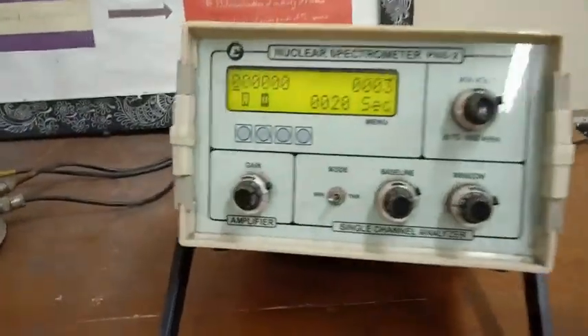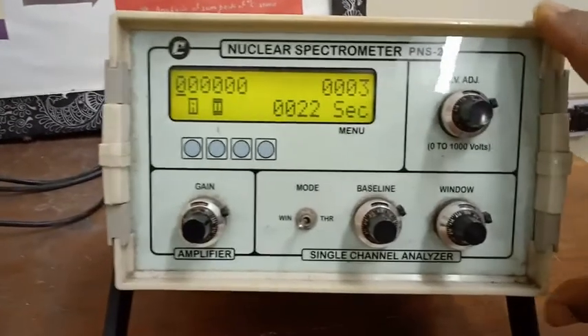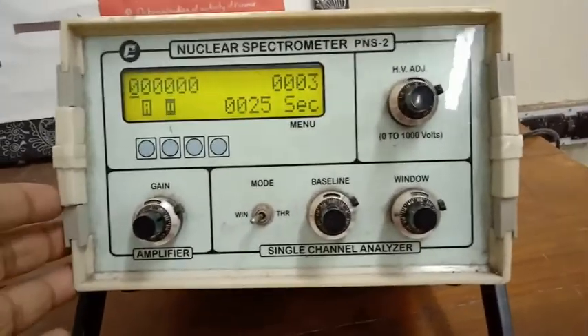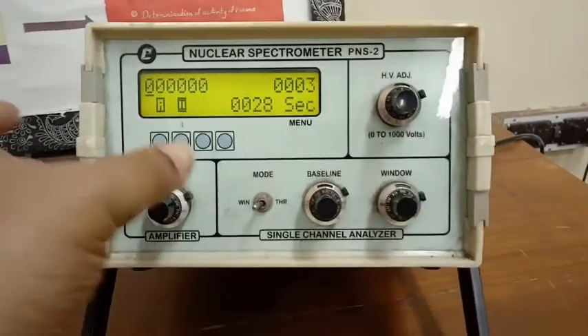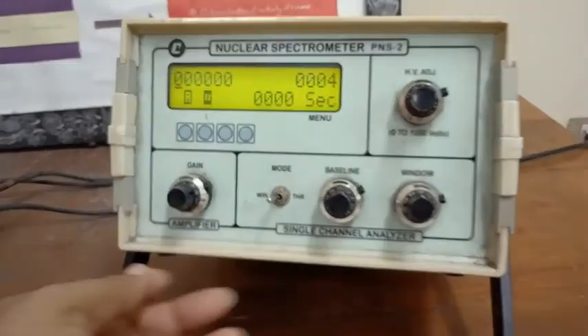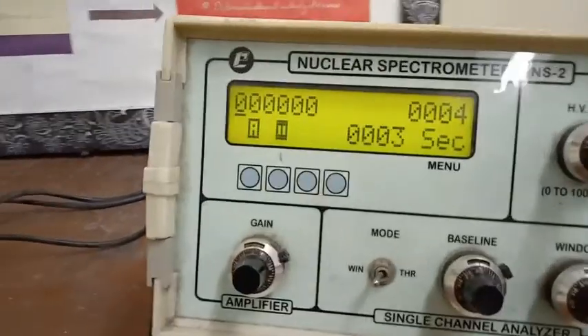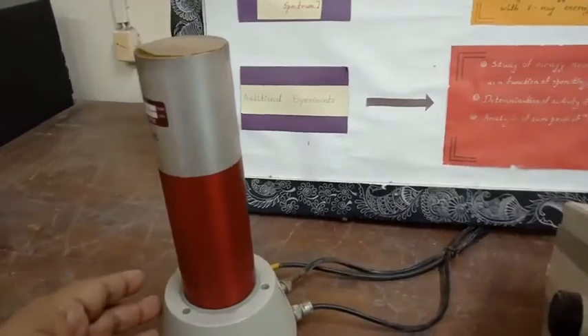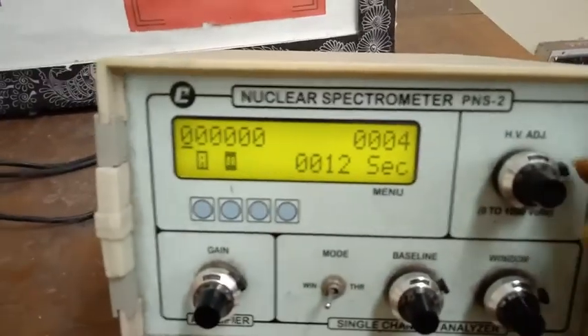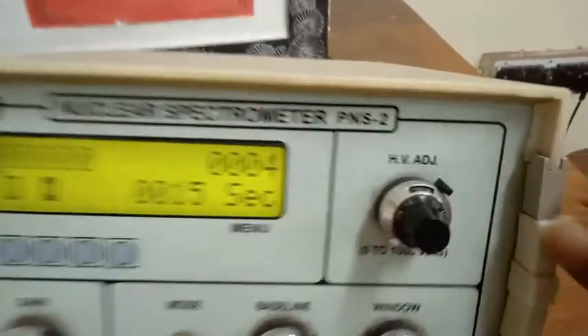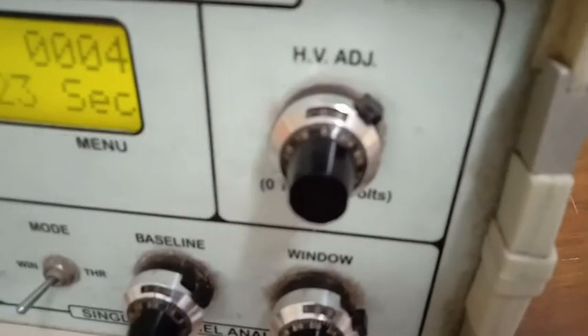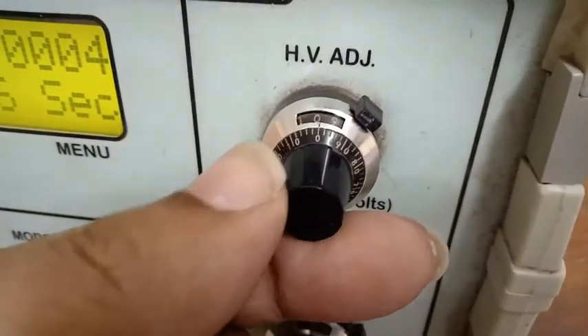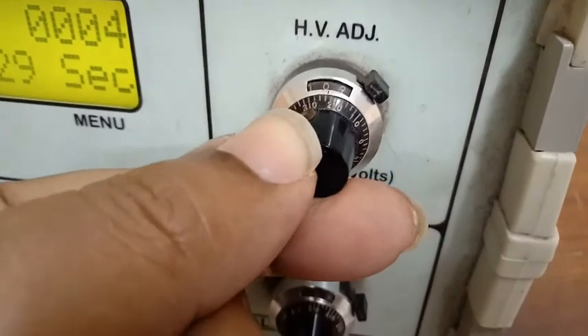Now regarding this setup, which is a combined box containing both the amplifier, this part, and the single channel analyzer, okay. Before I proceed, let me tell you that the detector we are going to use here has an operating voltage of 600 volts. So let me set it. This is the high voltage knob. As you can see over here, high voltage knob. Yes, so now I am going to turn it to 600 volts, right?